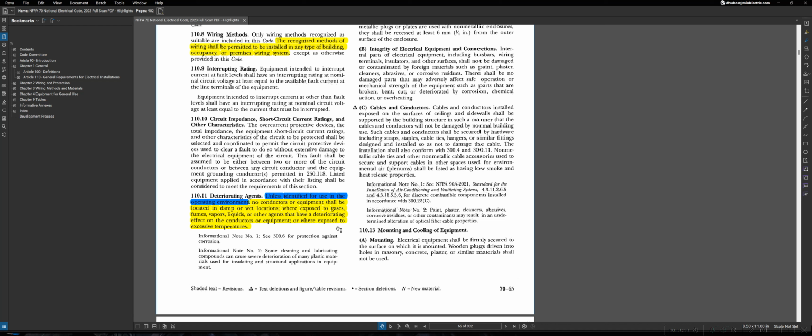And that's a very common thing. So, for instance, THWN is denoted as being allowable to be installed in a wet location. This isn't some type of oddball requirement, and it's something that's often overlooked because it's so common in the industry, but that is an NEC requirement.